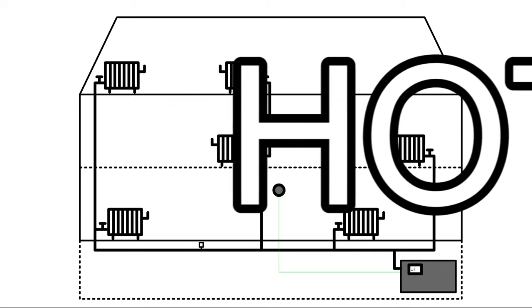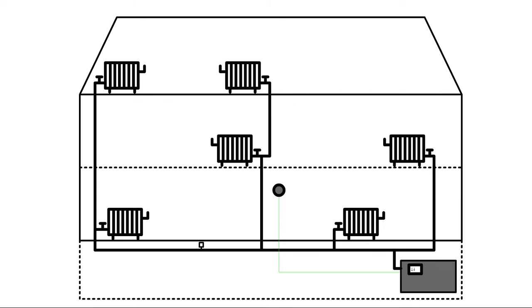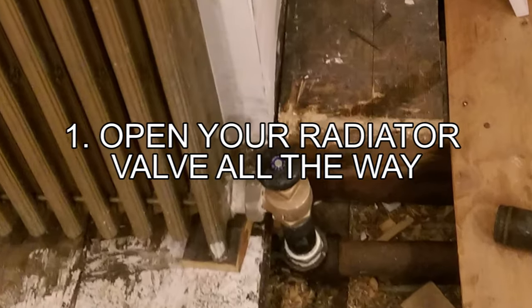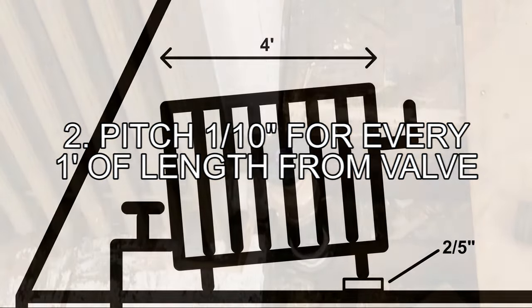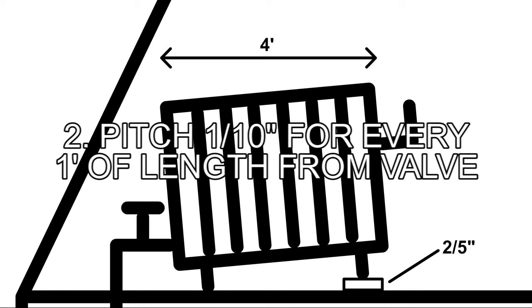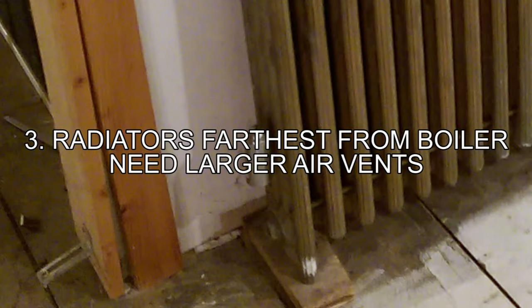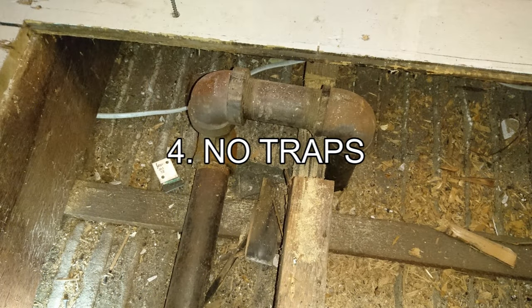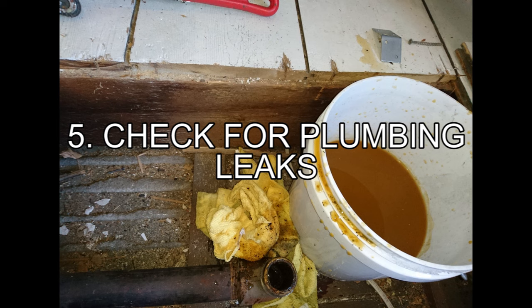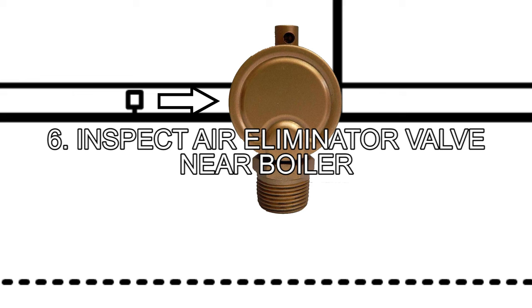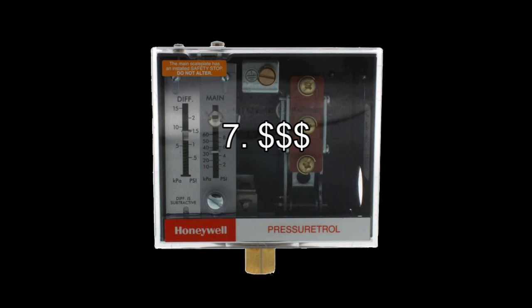In summary, here's your list of hot tips to fix your cold radiator, ordered by simplicity. 1. Make sure your radiator valve is all the way open. 2. Ensure your radiator is pitched to allow for the proper drainage of water. 3. Have an appropriately sized steam vent installed on your radiator. 4. Do not have any traps in your plumbing. 5. Check for any leaks from your plumbing, including the joints. 6. Inspect the air vent near your boiler for proper function, and clean it or replace it if you have to. 7. Lastly, you can fund this whole venture by saving some money with a properly set Pressuretrol.